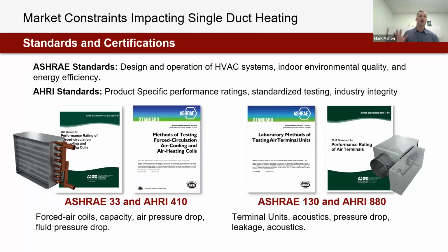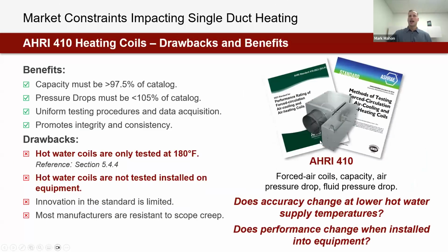And so when we look at water coils, we have ASHRAE standard 33 and AHRI 410. When we look at terminals themselves, we have ASHRAE 130 and AHRI 880. And the really important standard for us to discuss right now would be the AHRI 410 heating coil standard. So this is the performance rating of forced circulation air cooling and air heating coils. And this is the scope in which manufacturers play when we think about developing, innovating, creating new hot water coil product. And there's a lot of benefits to this standard.